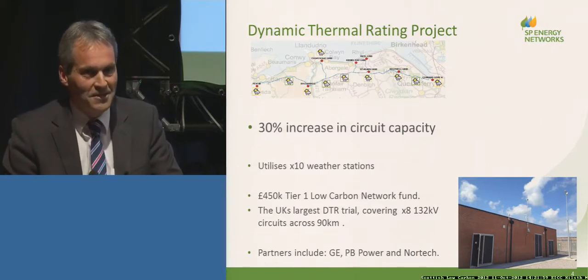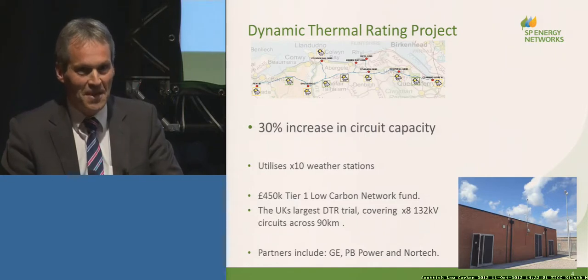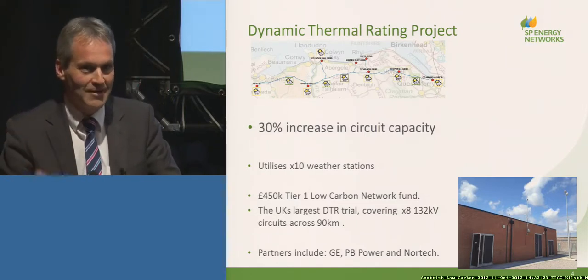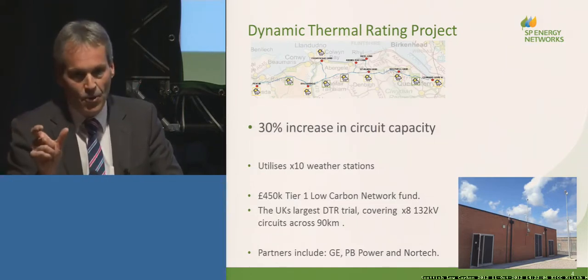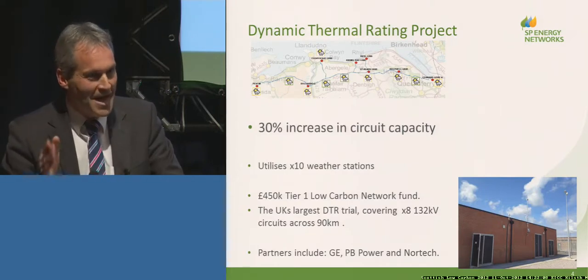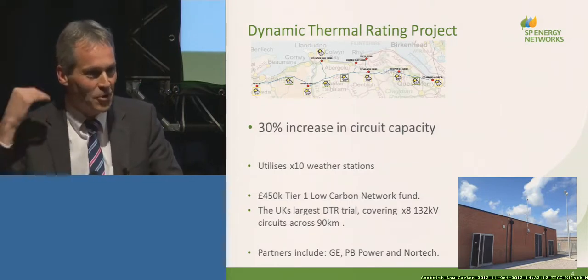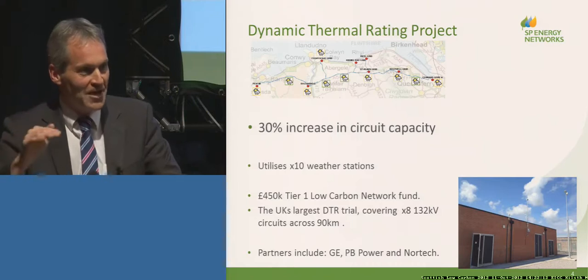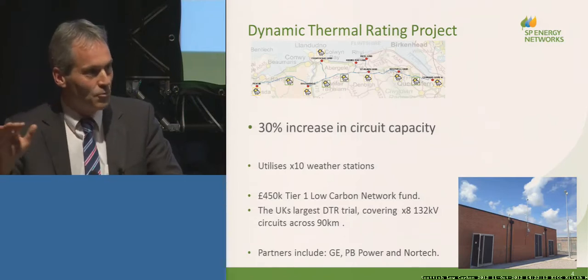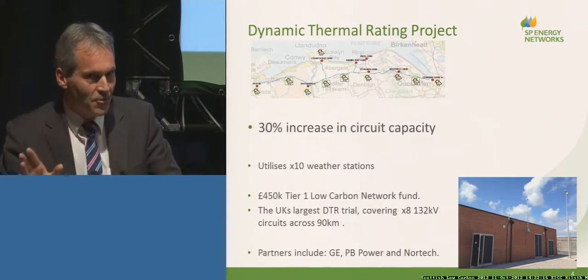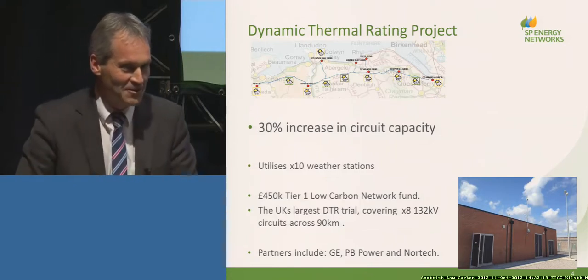We have basically two ratings in the year, a winter rating and a summer rating, that determine the limit we apply to our lines. In actual fact, when it's windy and you've got a cooling effect going on, you could actually get a lot more out of that line than you're achieving. It's a very straightforward principle - I don't think anyone in the room will have any difficulty understanding that.